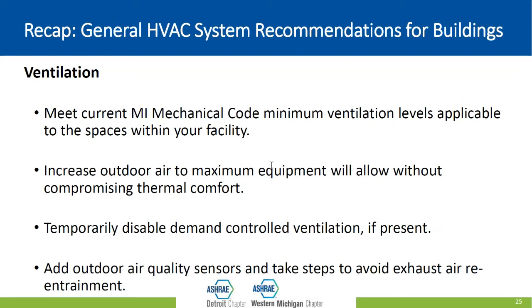We want to make sure that we increase our outdoor air ventilation as much as we can, right, without compromising the ability of the equipment to meet our set points, right? Remember that if you bring in additional air, that air's got to be heated and cooled and humidified and then moved around. And that's going to take energy and it's going to take extra capacity. And we want to make sure that when we're bringing in more outside air than we used to bring in, in the wintertime, can we still get the building up to 68 degrees, right, or 69 or 70 or whatever your set point happens to be?